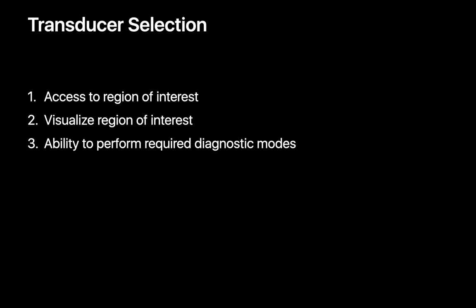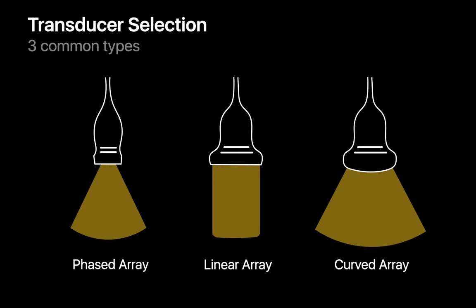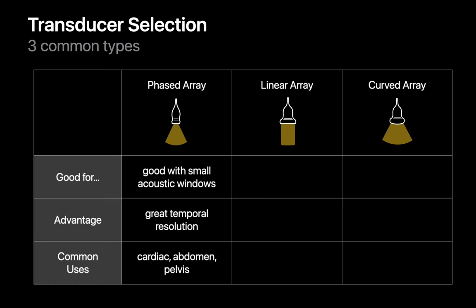Transducers come in different types, with different head shapes and sizes. Three common types are phased array, linear array, and curved array transducers. Phased array transducers are excellent when access windows are limited, such as between two ribs. They provide a fan-shaped image and great temporal resolution, which is crucial for imaging moving structures like the heart. They're also often used in abdominal and pelvic imaging.